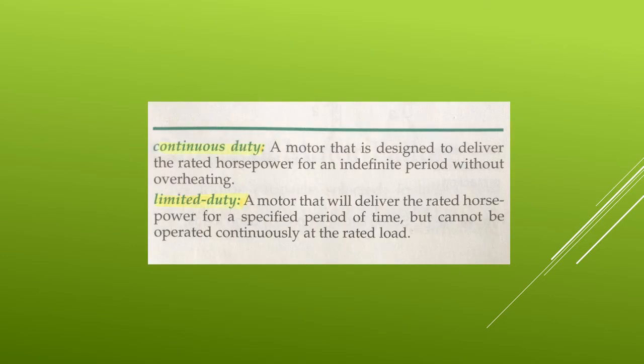Motor duty. Motor design has an influence on the capacities of the controller and fuses used with a motor. All electric motors are designed for either continuous or limited duty. Motors designed for continuous duty will deliver the rated horsepower for an indefinite period without overheating. General purpose motors should always be continuous duty type.